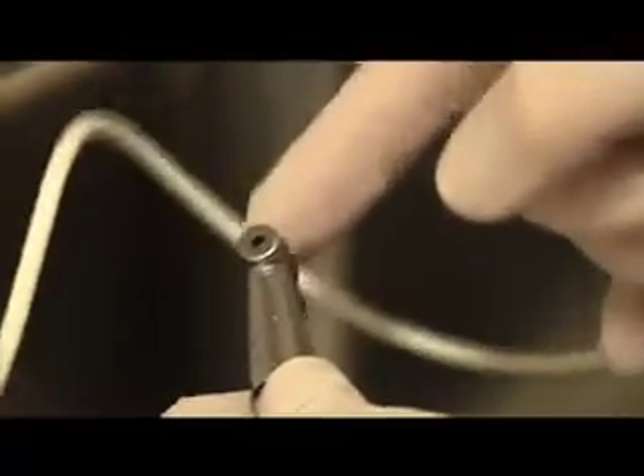Also, at the end of every case, you should clean and lubricate the harvester micro punch head. You should never use a cannula cleaner or pipe cleaner on the head because it may dislodge the rubber O-ring inside, and you would need to have that replaced. We recommend using a water pick. Alternate methods would be to use a spray bottle or a syringe with water to clean the head of debris. After you have finished thoroughly cleaning the punch head, soak it in a sterile solution.